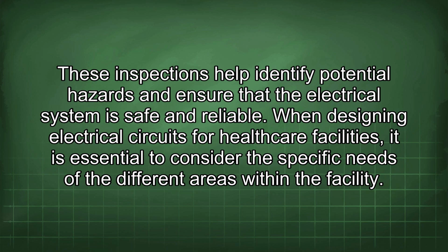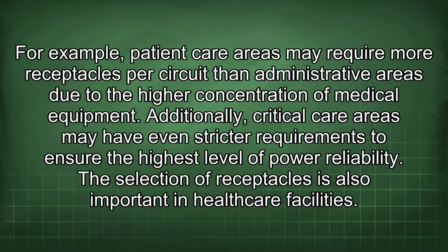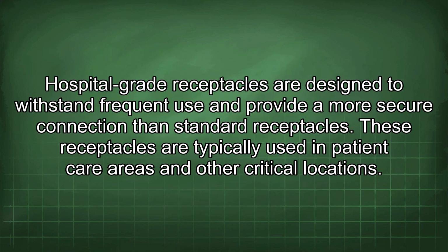When designing electrical circuits for healthcare facilities, it is essential to consider the specific needs of the different areas within the facility. For example, patient care areas may require more receptacles per circuit than administrative areas due to the higher concentration of medical equipment. Additionally, critical care areas may have even stricter requirements to ensure the highest level of power reliability. The selection of receptacles is also important in healthcare facilities. Hospital-grade receptacles are designed to withstand frequent use and provide a more secure connection than standard receptacles. These receptacles are typically used in patient care areas and other critical locations.